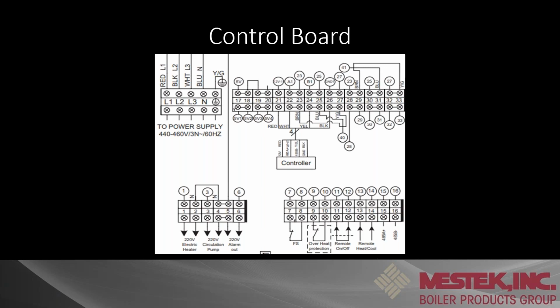Now, if we look down to the bottom here, we'll see that we have 220 volt electric heat. So we do have an output to kick on electric heat. I could also see this output being used to kick on a backup boiler with some type of relay there. Next would be 3 and 4, which would be your circulator pump out. So if we're doing dedicated pumps on this heat pump, we're going to use that to power our pump. And then 5 and 6 will give you an alarm.